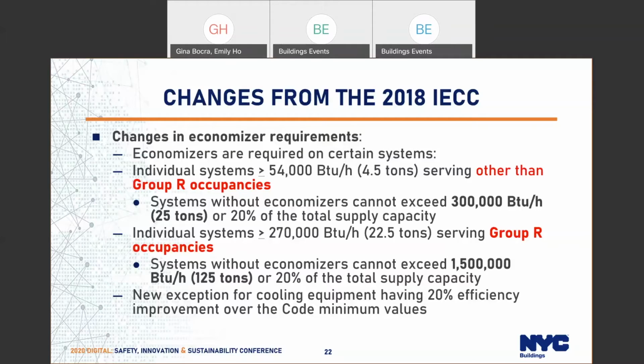There is another provision. We've also gotten some questions so far regarding the 2020 code that a lot of buildings would still be pushed into the ASHRAE provisions because of the Group R requirement. You still have an aggregate capacity of 1.5 million that cannot be without an economizer. But there's an important exception that was added. So there's an exception now that says you don't have to do any economizer on any equipment, regardless of the size, as long as it has a 20% efficiency improvement over the code minimum values. So if you have high efficiency equipment in your building, you do not have to do an economizer.